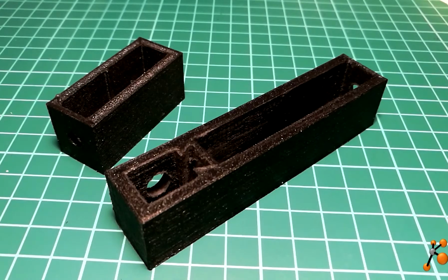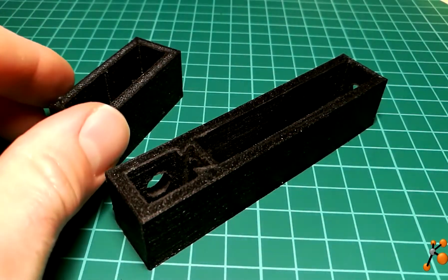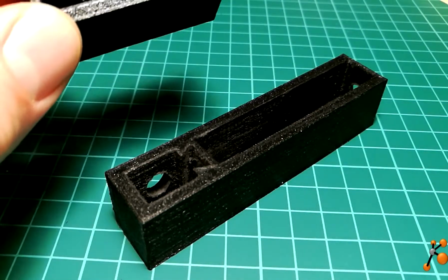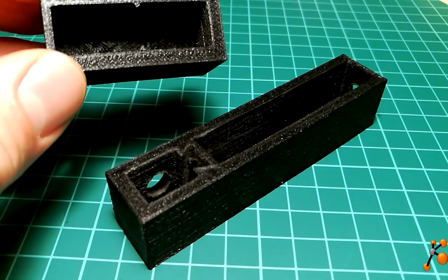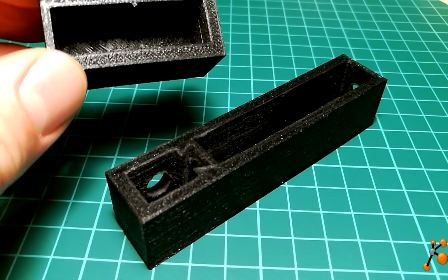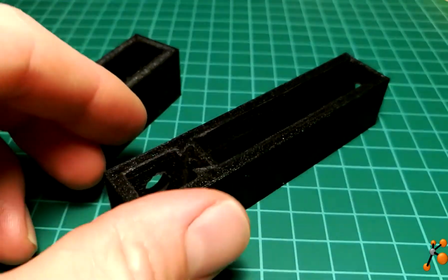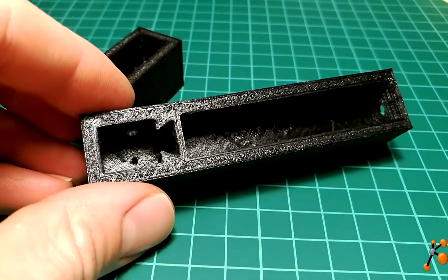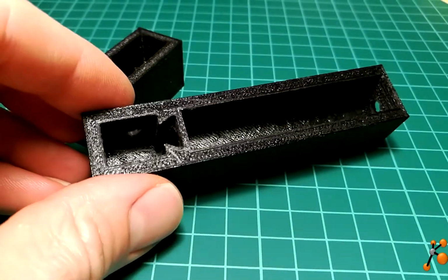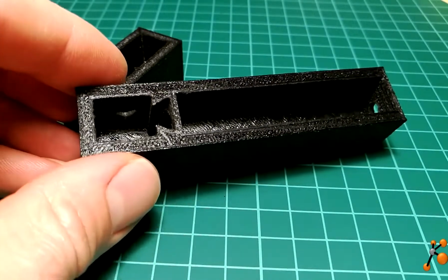Hi everybody, welcome to the third video of the vlog, and today we are going to continue the project concerning the development of a fluorescence detector. On the left here we have the first prototype that we designed and realized, where the distance between the lens and LED was not good. Then we designed a second prototype where we adjusted this distance to 68 mm between the LED and lens.